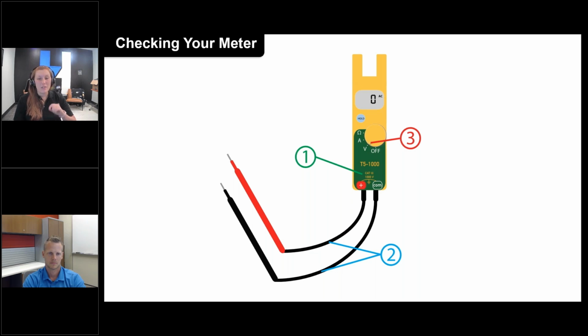There are also times where putting leads on equipment, if it's not properly rated, could be the cause of an incident. So have a good category rating. Most often Cat 3 600 volts is what we see people need. Cat 3 1000 is even better, Cat 4 600, Cat 4 1000, but minimum Cat 3 600 volts. And then check your leads as well. Make sure they're in good condition while you're doing this test. You don't want any exposed metal or nicks or broken handles, and so forth. And they also need a proper rating.